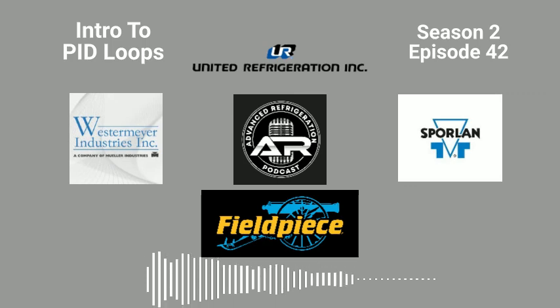With pulse valves, you could throw the best tune in the world in there, but it is what it is. It's a solenoid pulsing liquid, so it's going to be choppy no matter what. You can make it look somewhat okay, but you're going to have peaks and valleys and mountains. A pulse valve will never be what a stepper is. I don't care who says what, it's never going to control as good as a stepper.